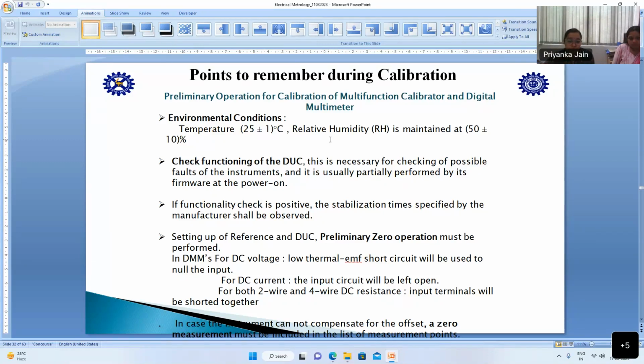Next, the last one, is 2-wire, 4-wire DC resistance measurement. The input terminals will be shorted together and then connected and tested. So in case of measurement, we need to compensate for the offset. If you are not getting a zero value at the initial stage, you need to measure the zero value using the instrument, and that measured value should be included in your measurement points. Otherwise, there is no meaning in calculating the values for different points. If the zero is adding additionally to your values, you should either subtract or add it to your values. These are some of the points you need to keep remembering during your calibration.